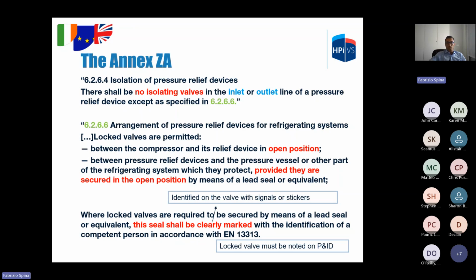Isolating valves can't be installed in the inlet or outlet of a pressure relief device, except as specified in this point. Locked valves are permitted in open position between a compressor and its safety device, and between pressure relief devices and the pressure vessel which they protect, provided they are secured in the open position by means of a lead seal or equivalent. Equivalent means a system where accidental operation is prevented. For example, to close a valve, a preliminary action is required, like removing the seal, before the actual closing operation can be performed.